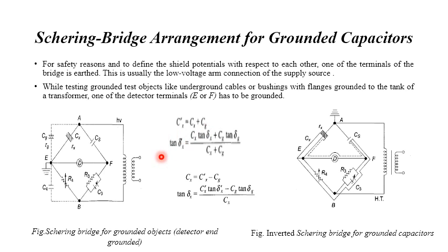Then we can calculate. The tan delta loss angle measurement will give rise to a parallel combination, and after simplification, Cx tan delta x plus Cg tan delta divided by Cx plus Cg. Hence the actual capacitance and the dissipation factor of the test object can be written as Cx is equal to Cx dash minus Cg. So this will give rise to the equation for tan delta x. This is the final one.